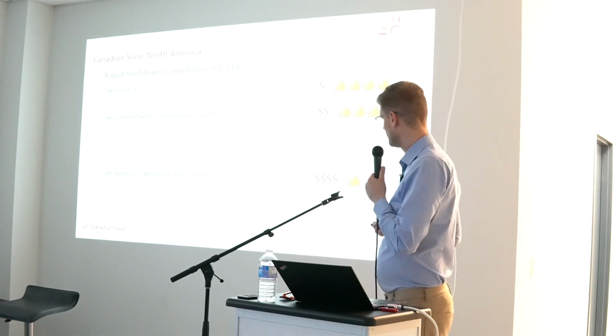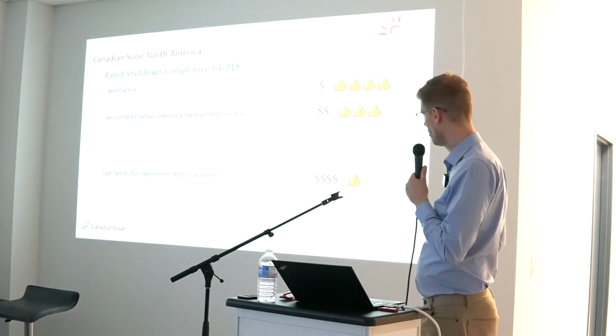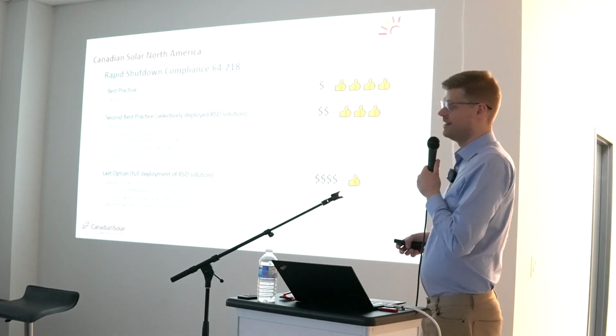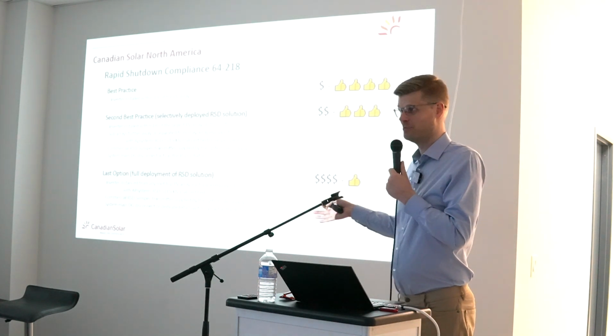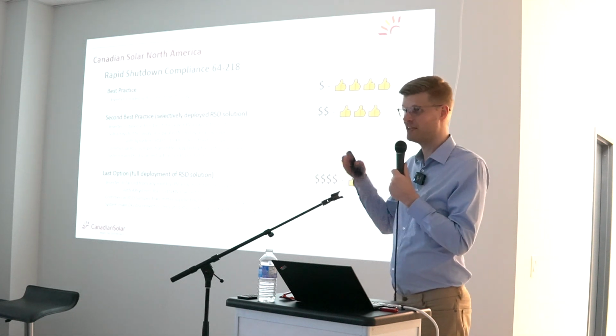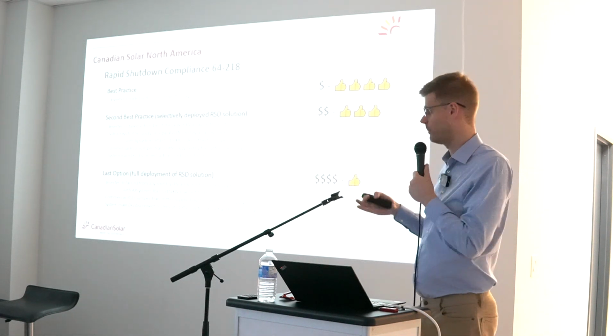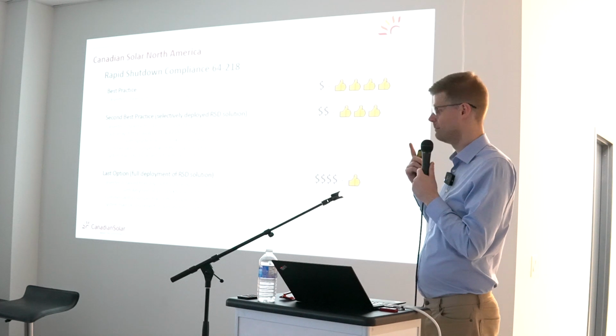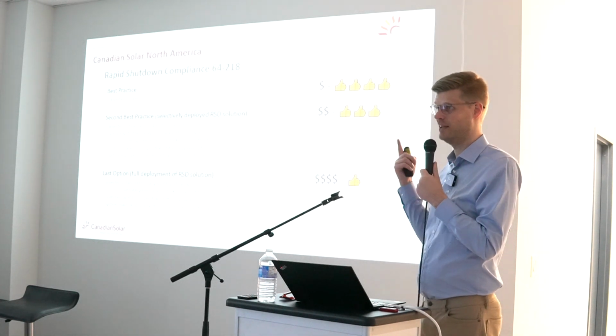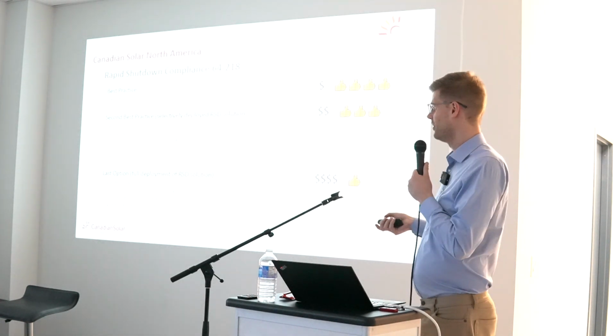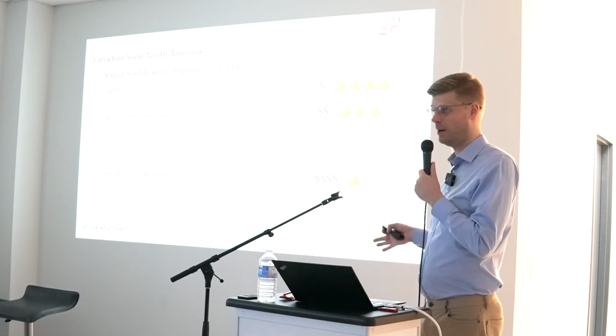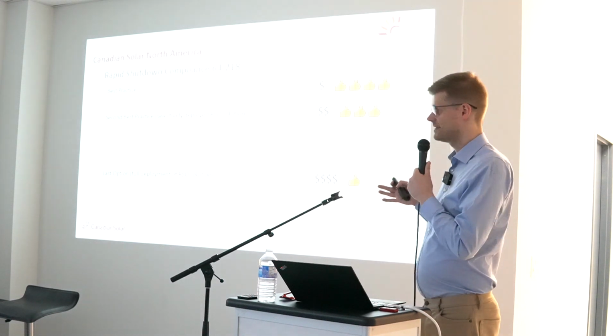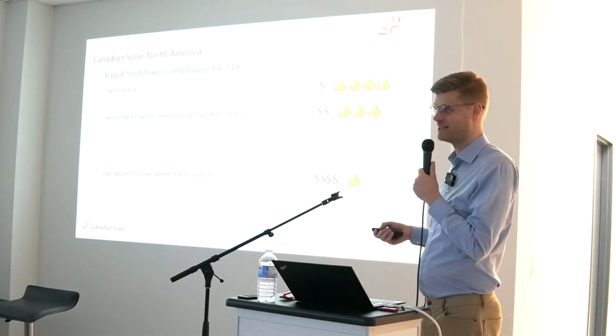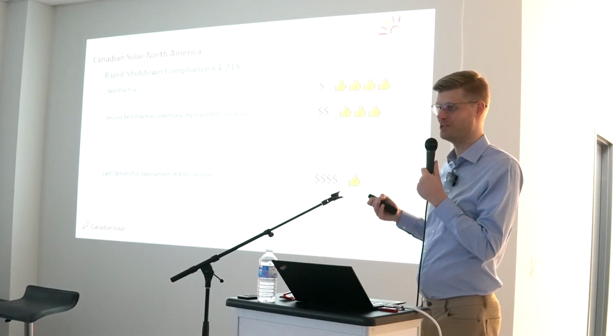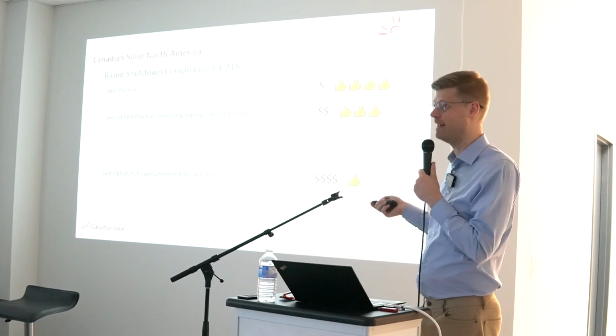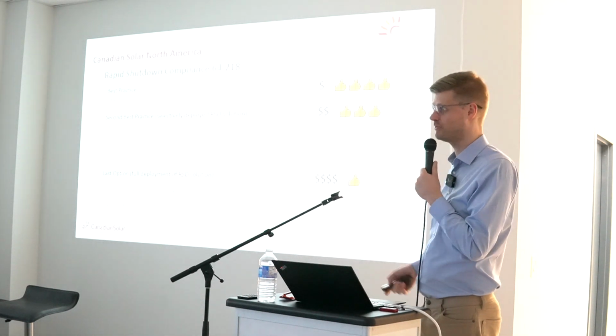The last option, and that has the highest dollar and only one thumbs up. You can place the inverter in your electrical room, but then you're forced to have every single panel of your system equipped with rapid shutdown. That is the most components, the highest cost, and the least reliable system. So only do that if there are no other options. And we're happy to sell you APS rapid shutdown systems, but it's not in your own interest to have that many components on these large-scale commercial rooftop systems.